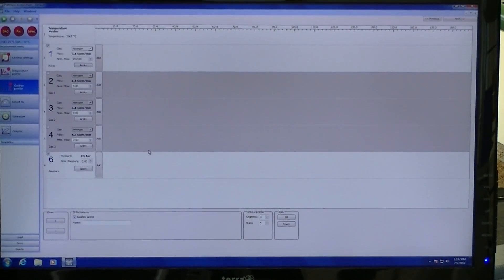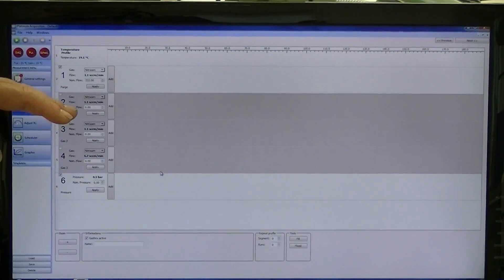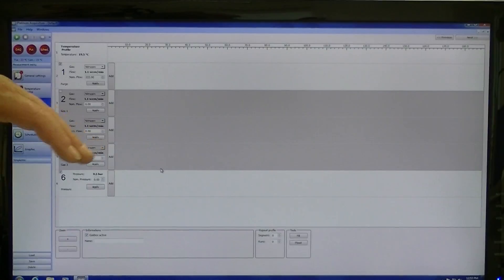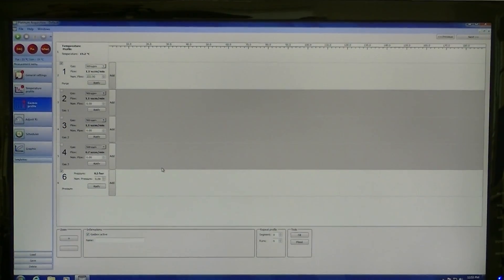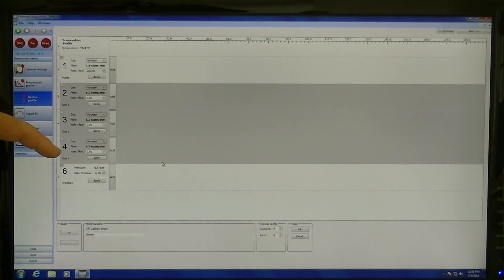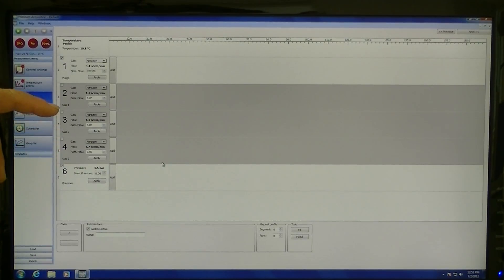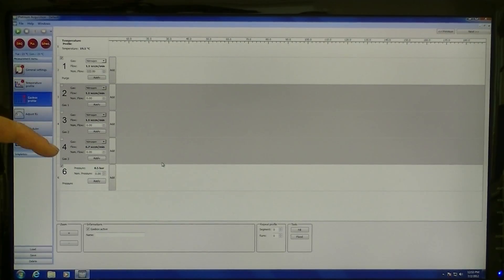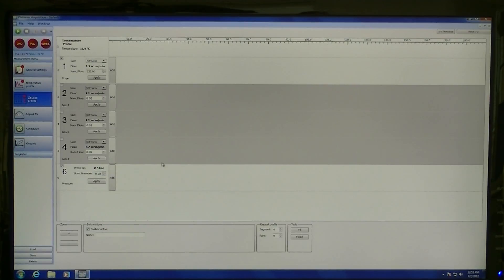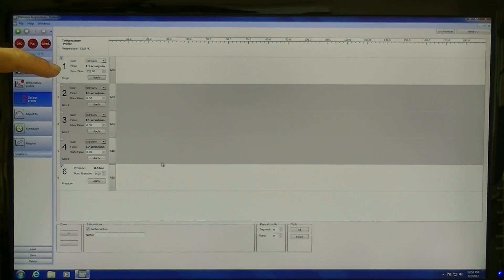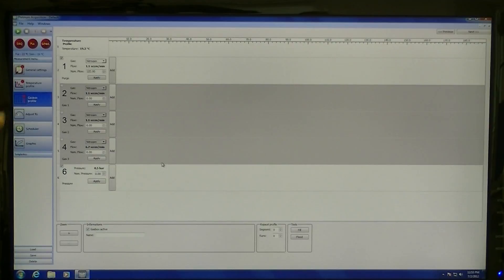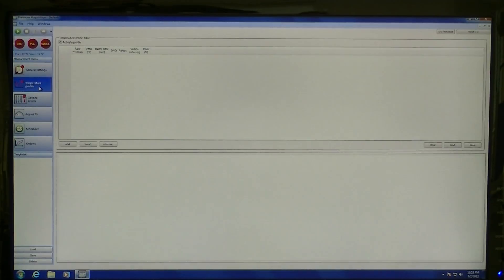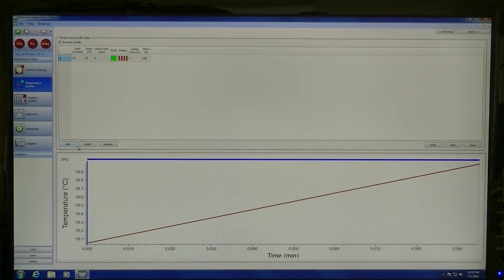Then you can program here gas control systems. You can have a purge gas which is used as a carrier gas for the MS or for the FTIR. You can also additionally use three additional gases for a chemical reaction or for any kind of other purpose that you can mix different gases. They can be all mixed here. And position number six is the pressure controller. You also can run pressure profiles. It's not necessarily one constant pressure. You can increase or decrease in pressure profiles. As well as you can also run increasing or decreasing in gas flows or constant gas flows. This is very flexible. Then you also can program here a temperature profile which is the temperature at the sample. You can run any temperature profile, any gas profile and any pressure profile.